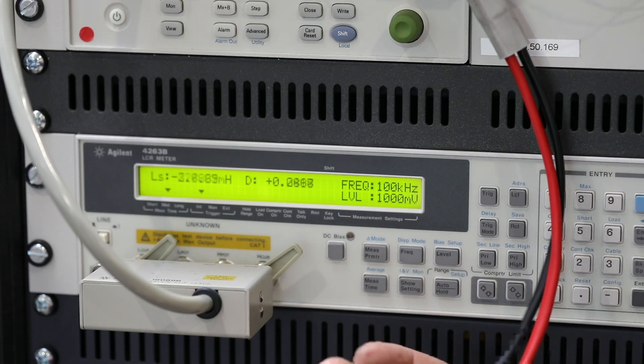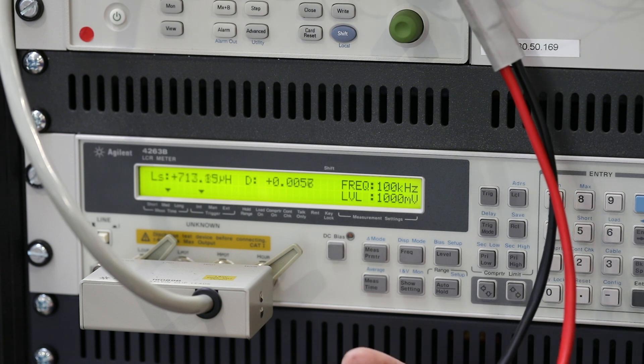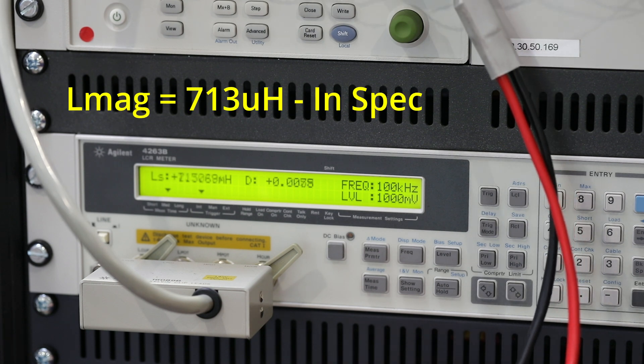And there we go, 713 microhenries is within specification for our primary magnetising inductance.